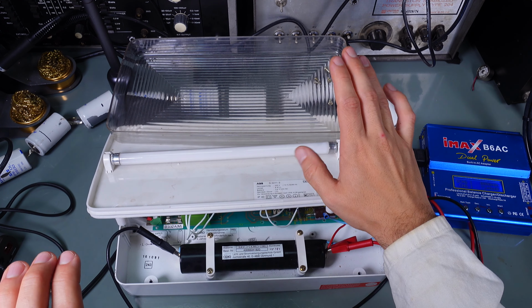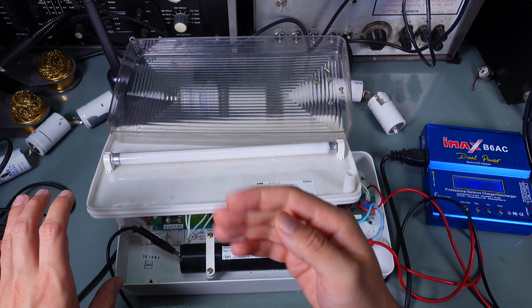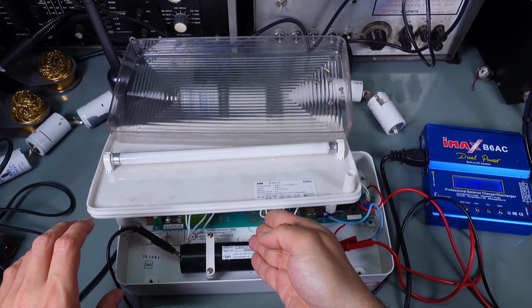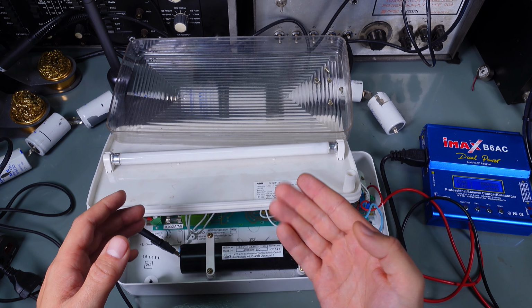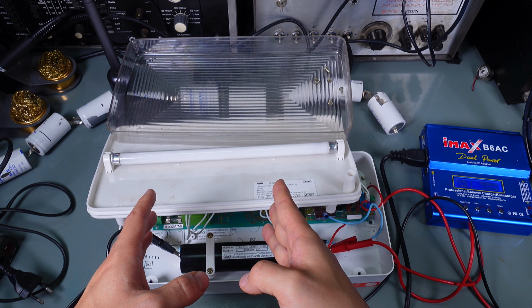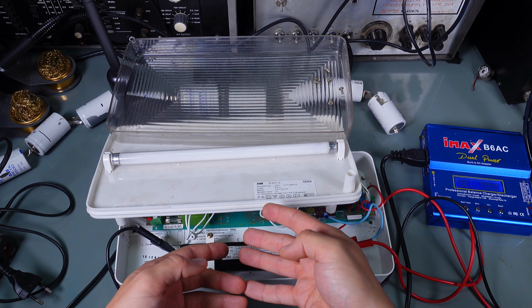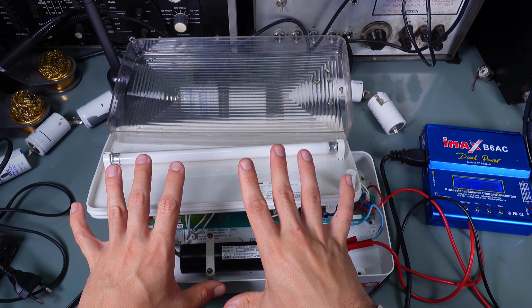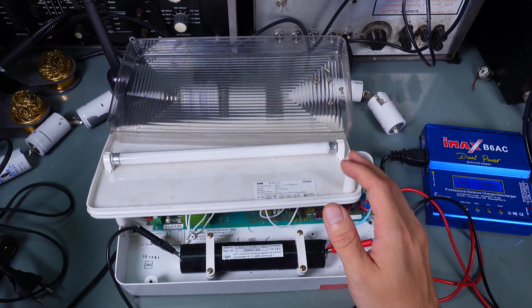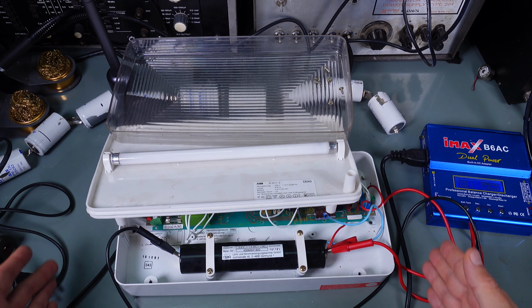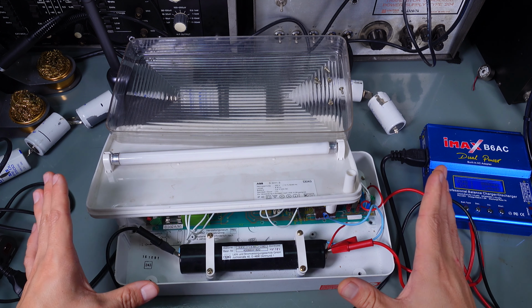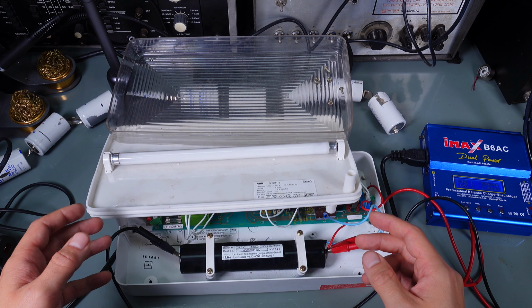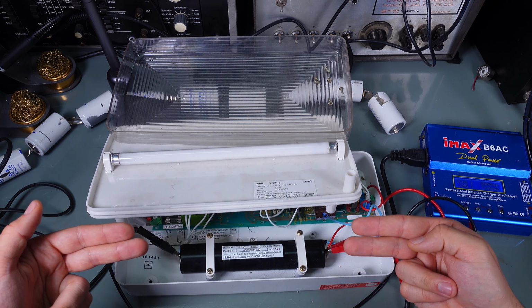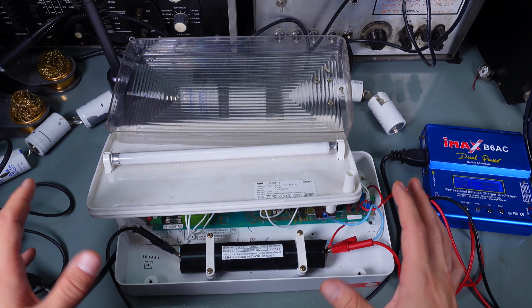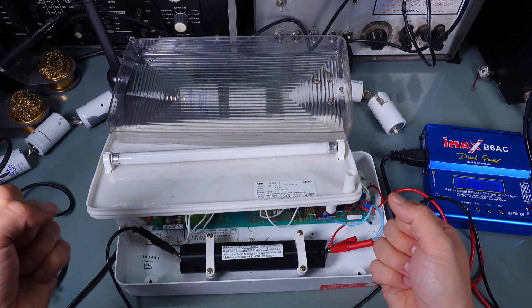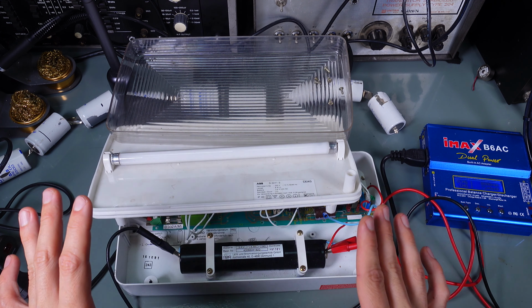Imagine a hallway during an earthquake or fire, and some metal structure beam pierces one of those light fixtures. Because they are self-contained, only that one will stop working or have an internal short; that one won't be operational, but the ones before and after are totally fine because they don't require any wiring in between. So you don't have a second emergency power line from a battery with a single point of failure. You've got a self-contained unit you can even pull from the wall and use like a portable flashlight. Absolutely beautiful.